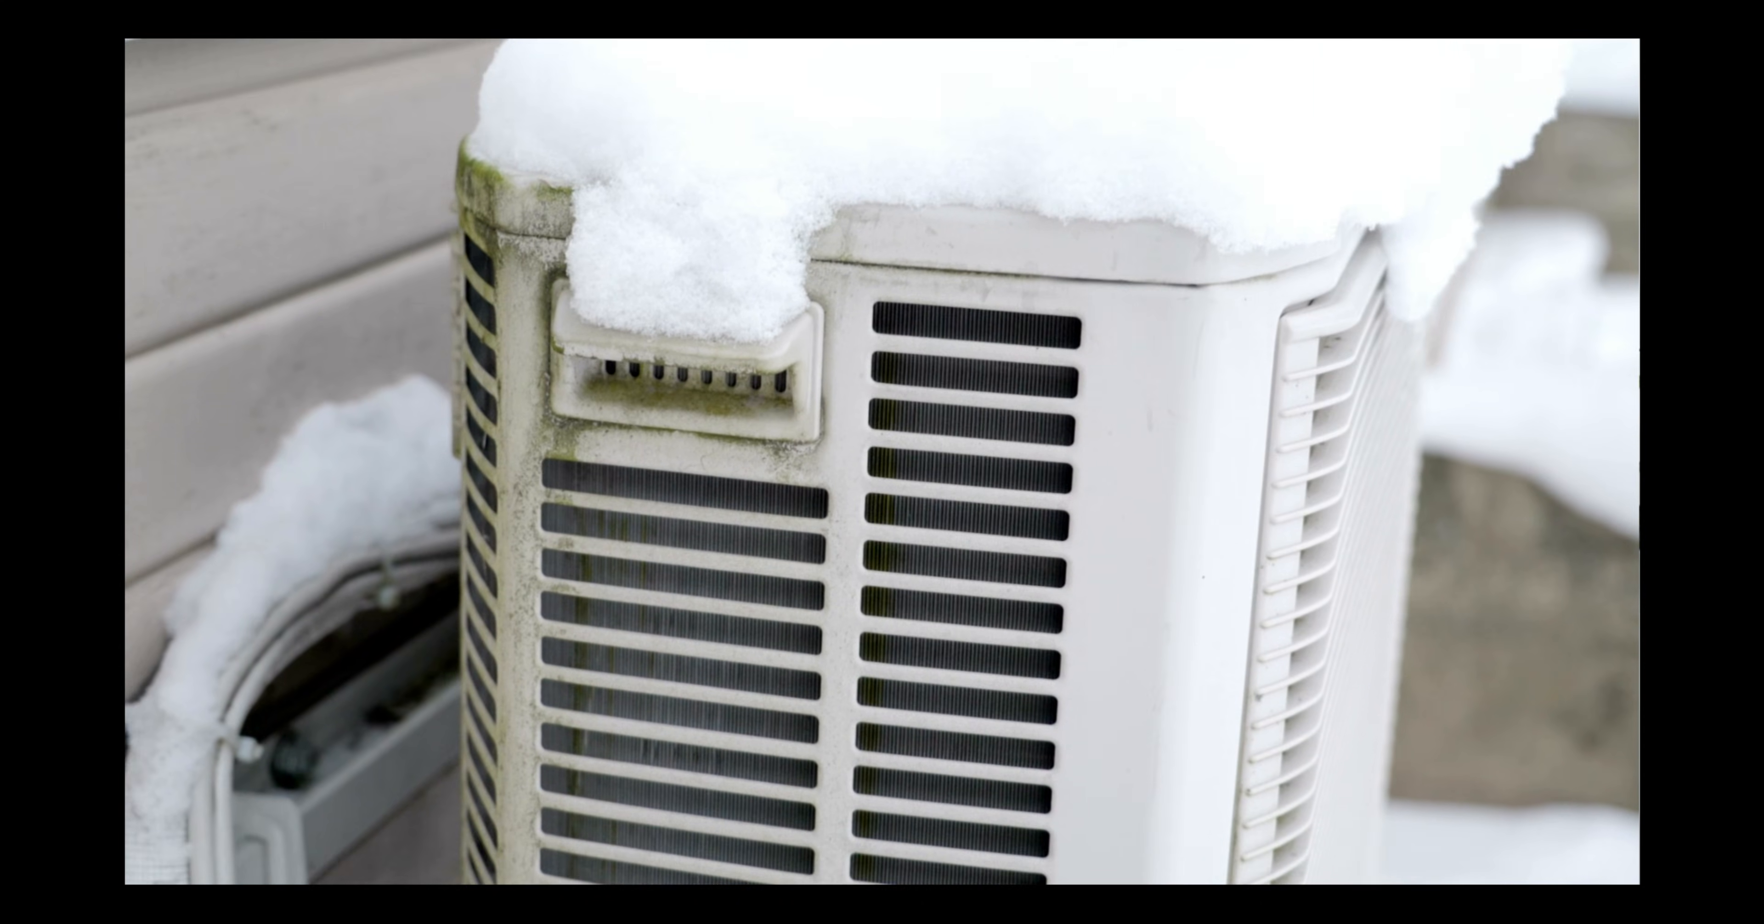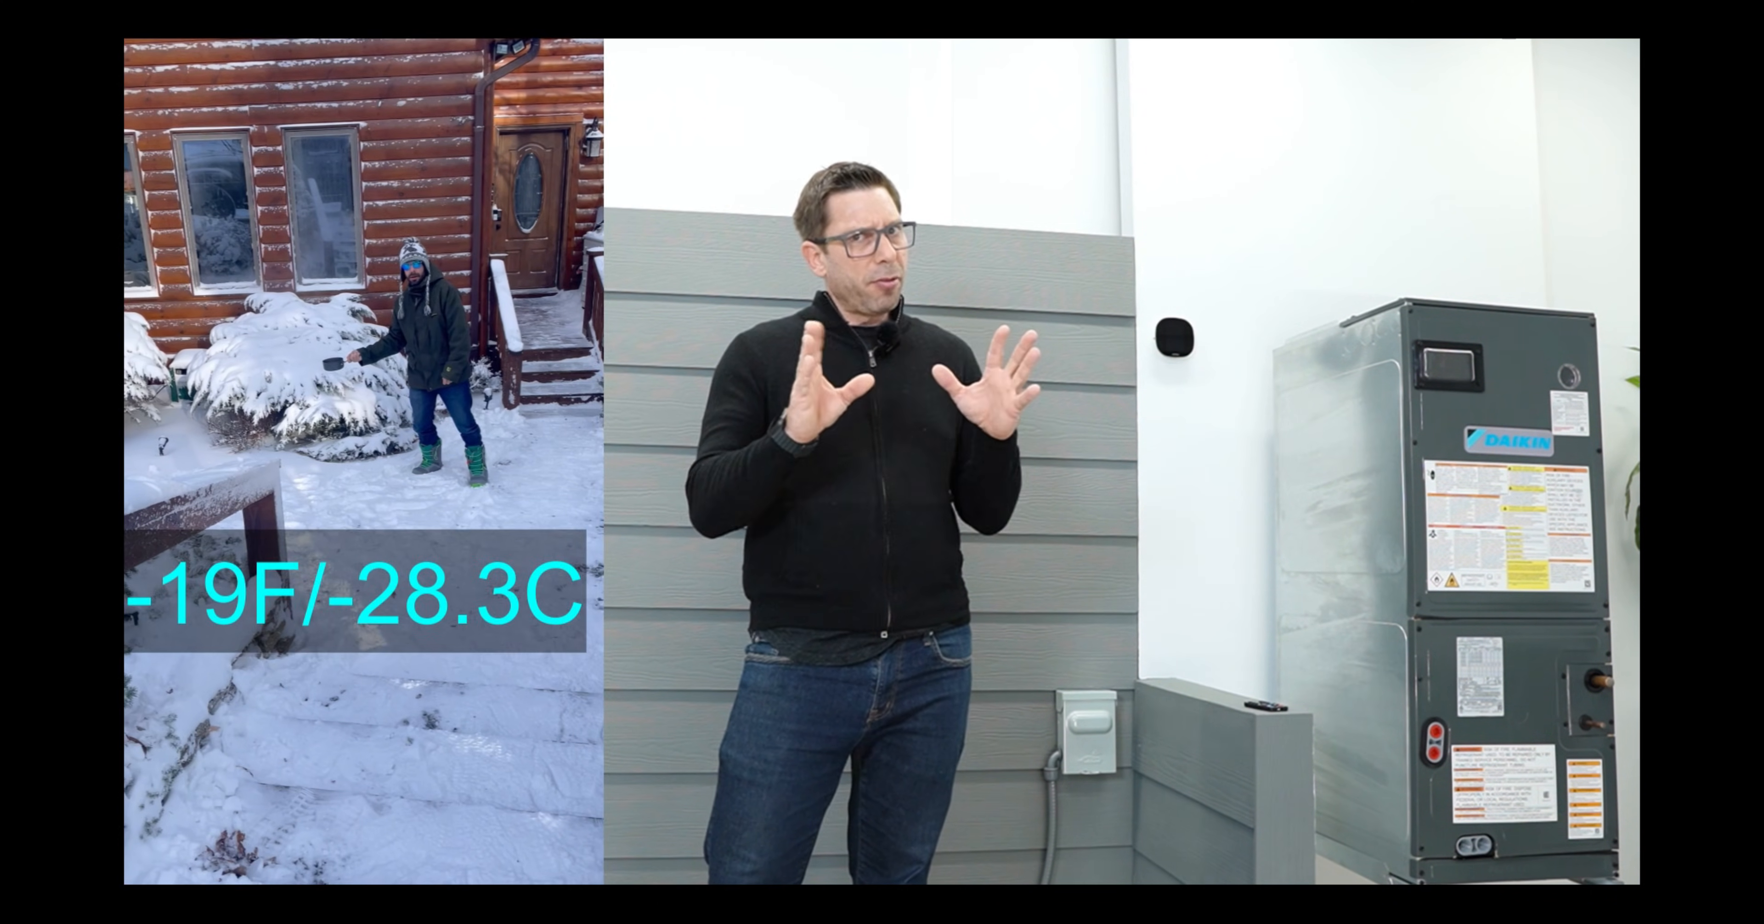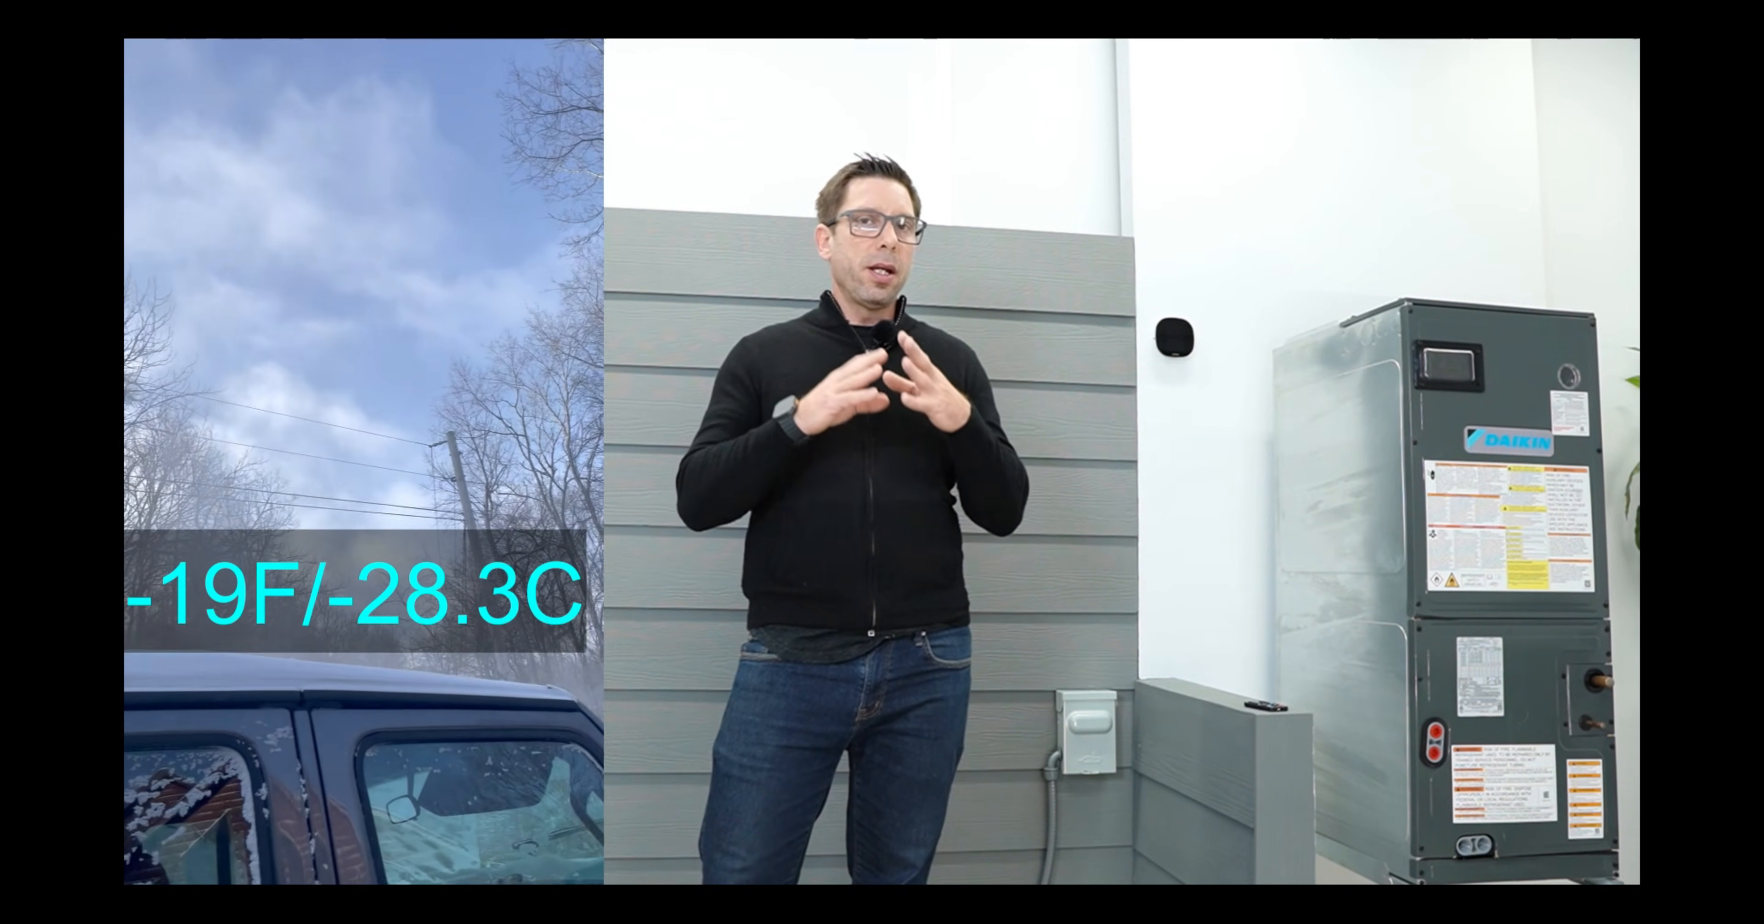So around the ski resort many people use heat pumps as their primary heat source. For example, the house in the background has a heat pump only. That's me in the picture, and on that particular day the temperature was at the record low of minus 19 degrees Fahrenheit, which is actually quite rare for this geographic location. I threw boiled water into the air as my son was filming me, and as you can see it immediately vaporized. Now was the indoor temperature comfortable? The heat pump was running in auxiliary heat only and still managed to maintain 57 degrees. Not very comfortable. And this was without the help of a gas converted fireplace. Later in the day the indoor temperature returned to normal setting in the upper 60s. And once the cold snap passed everything became comfortable again.